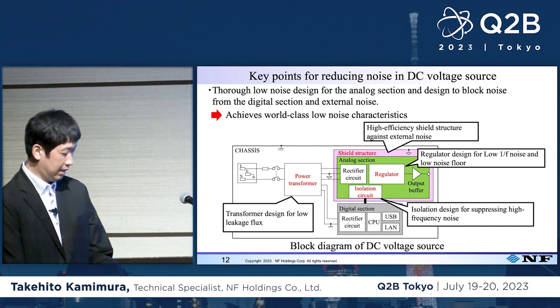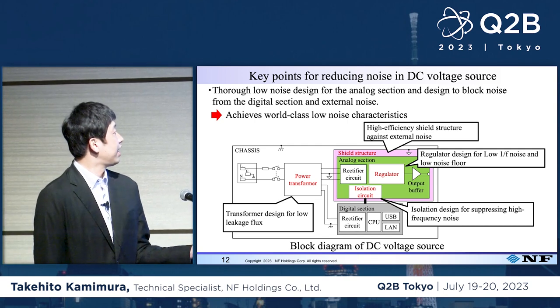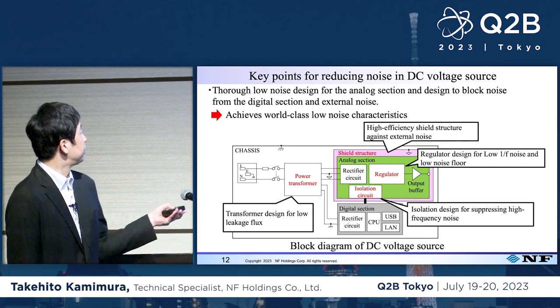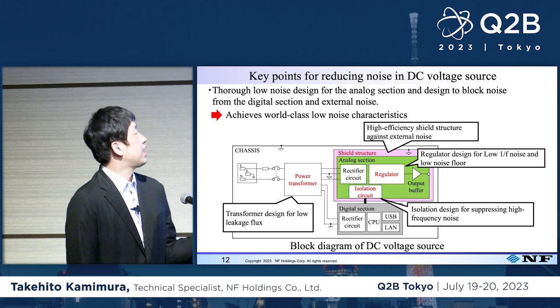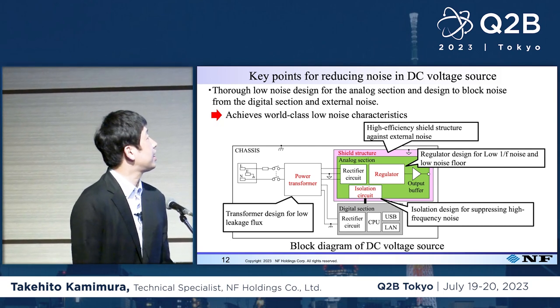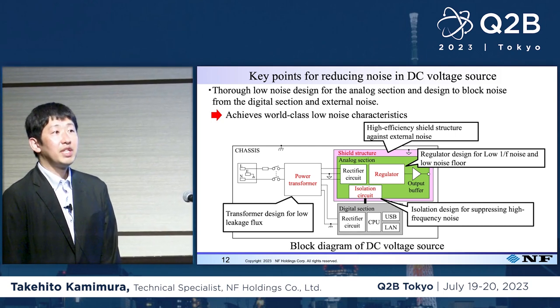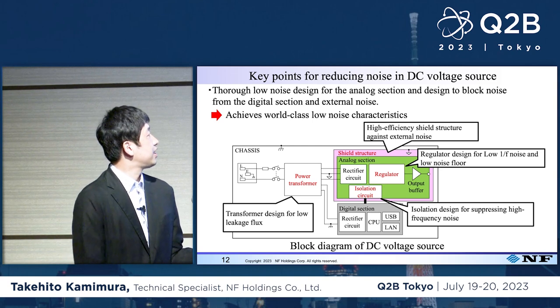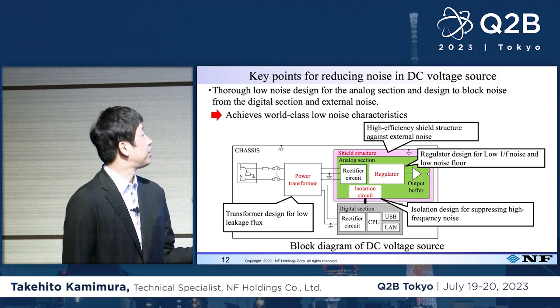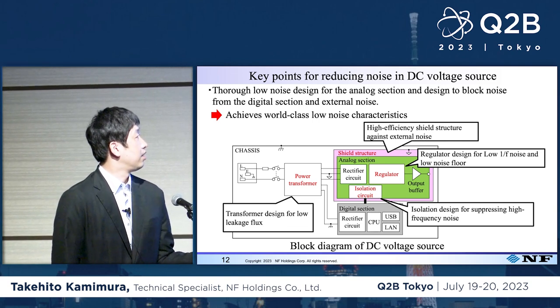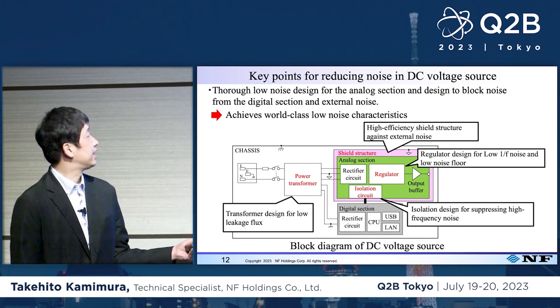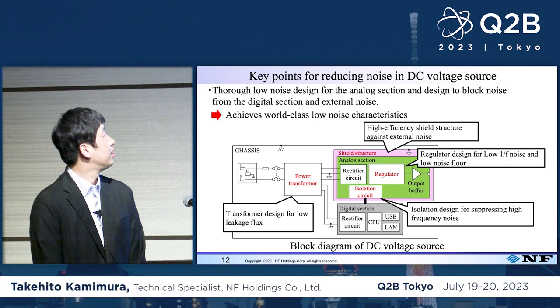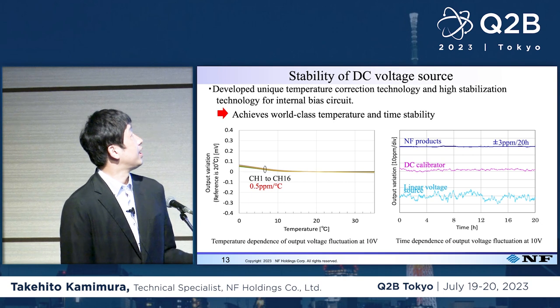Now I'd like to talk about our technologies to realize low noise. In the analog part, we designed the transformer so that it has low leakage flux. We also have a regulator design for low 1/f noise and low noise floor. For external noise, we have a high-efficiency shield structure. From the digital part, we designed an isolation circuit that blocks noise from the digital section. This isolation circuit can reduce high frequency noise. By combining these technologies, we realized the low noise products.